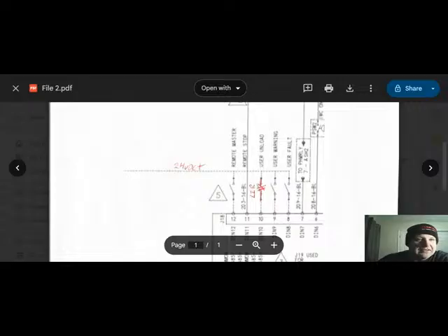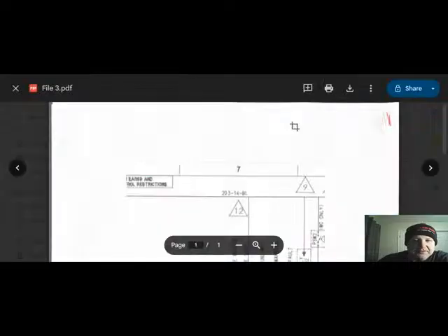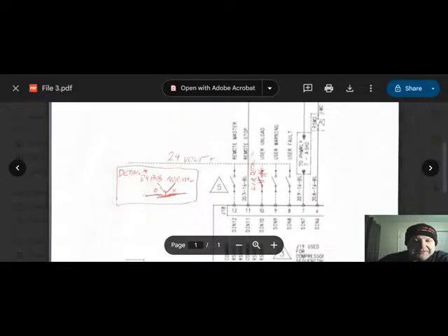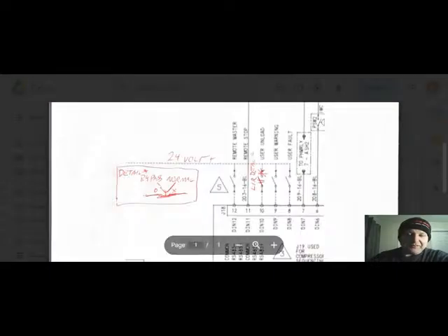If you wanted to take this to the next level, what I would do is put a manual bypass switch in. You just put a little two-position switch right into the door, next to the controller, whatever makes you happy. So that if you need to defeat this easily, let's say you're there after hours doing some service or troubleshooting, everybody's going home and you're still there, you just flip this switch to bypass, and now it will stop this signal from getting through here, and the compressor will operate as normal until you flip that switch back to normal.